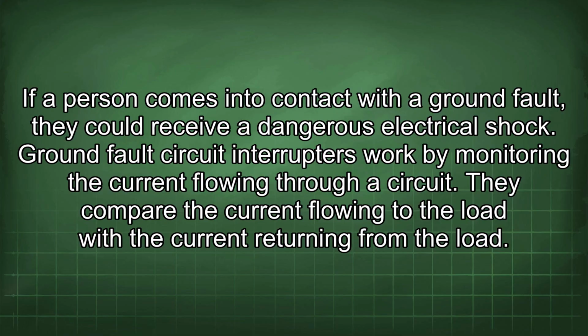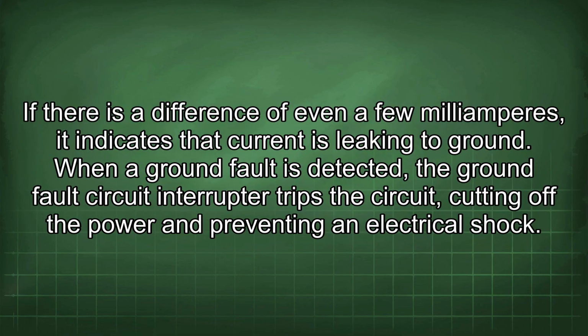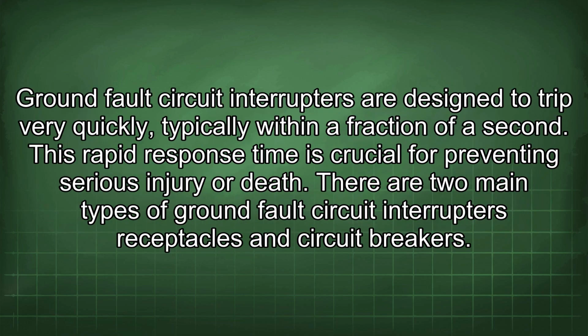Ground fault circuit interrupters work by monitoring the current flowing through a circuit. They compare the current flowing to the load with the current returning from the load. If there is a difference of even a few milliamperes, it indicates that current is leaking to ground. When a ground fault is detected, the ground fault circuit interrupter trips the circuit, cutting off the power and preventing an electrical shock. Ground fault circuit interrupters are designed to trip very quickly, typically within a fraction of a second. This rapid response time is crucial for preventing serious injury or death.